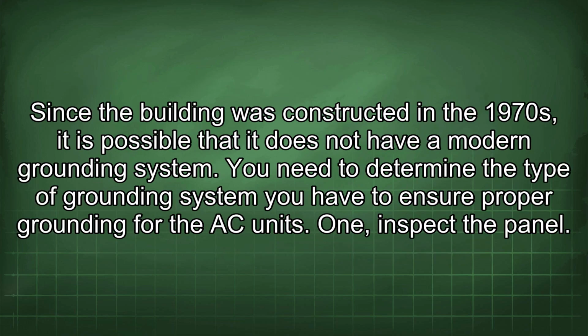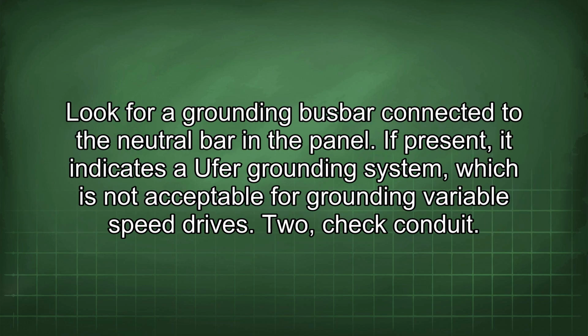Since the building was constructed in the 1970s, it is possible that it does not have a modern grounding system. You need to determine the type of grounding system you have to ensure proper grounding for the AC units. 1. Inspect the panel. Look for a grounding busbar connected to the neutral bar in the panel. If present, it indicates a Ufer grounding system, which is not acceptable for grounding variable speed drives.